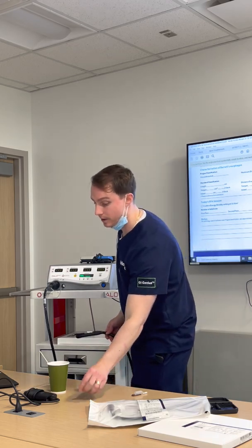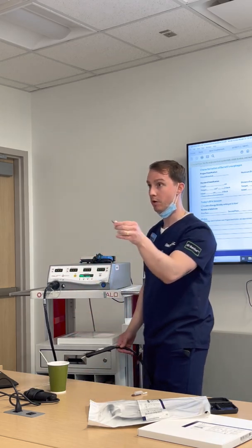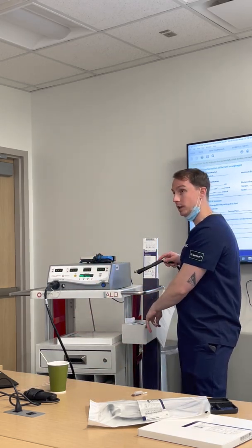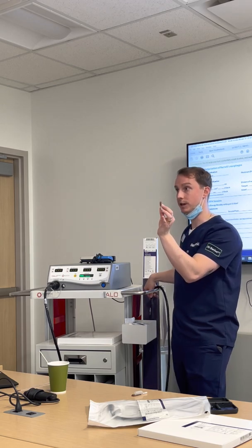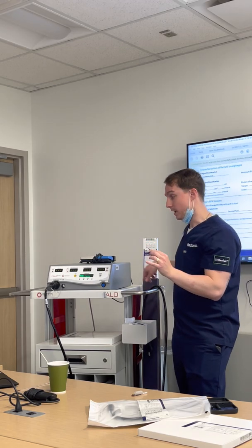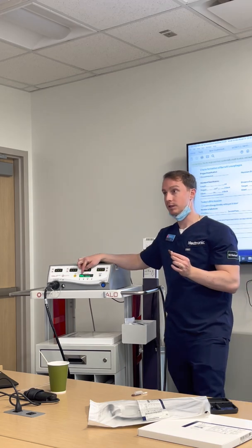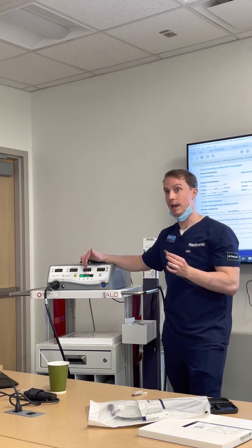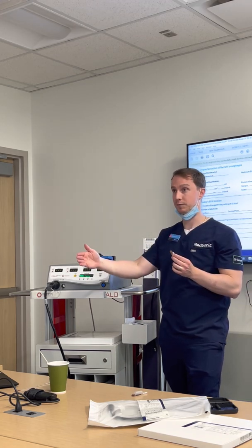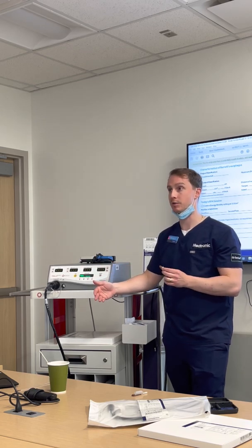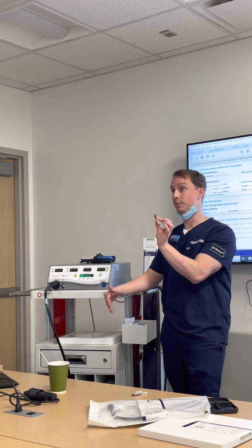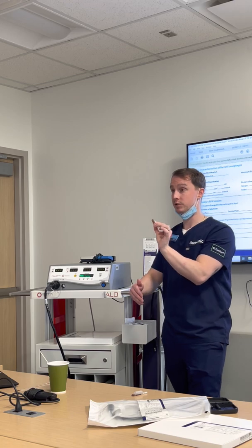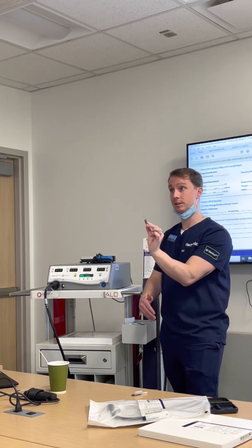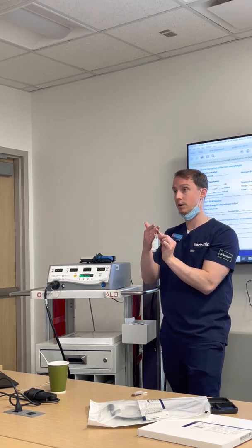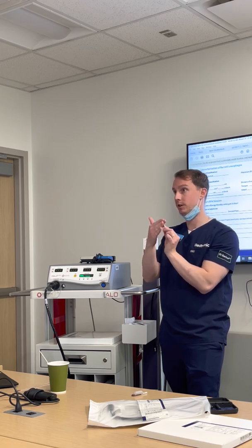Again, these focal catheters are rigid enough that they're not going to pull out and use a cleaning cap. They're just going to use the catheter to clean. A couple of takeaways: we want to be cognizant after each ablation that if it's saying anything but 100%, let's please let the physicians know we only got 80% energy delivered there. That could have been user error from the physician standpoint, maybe it wasn't flush up against the skin, or likely there's some coagulum or tissue attached to the catheter here.